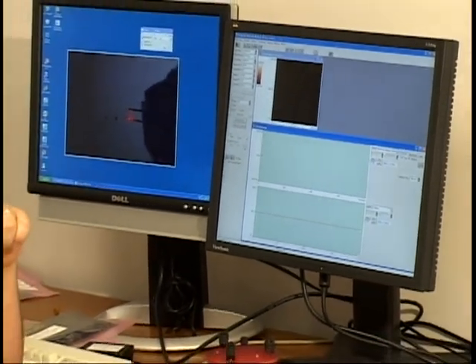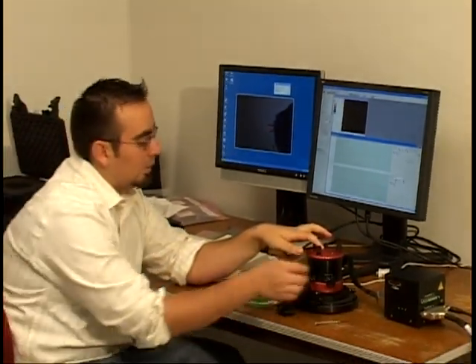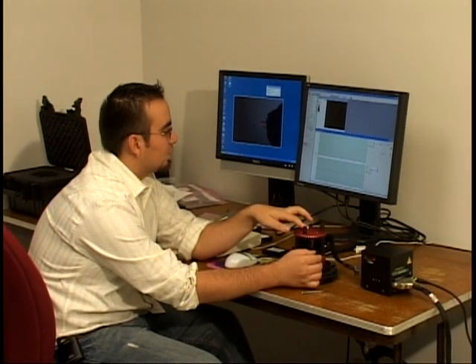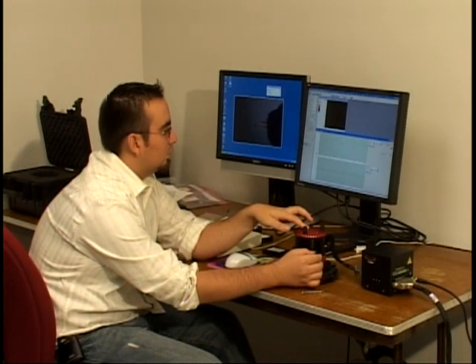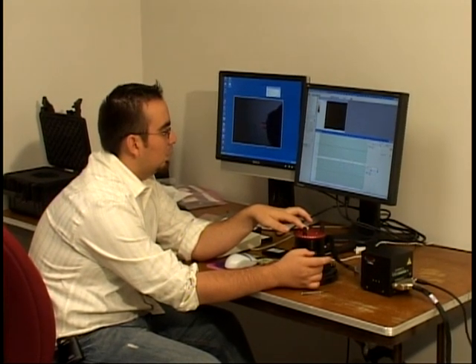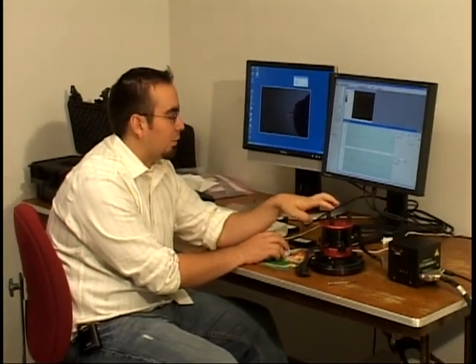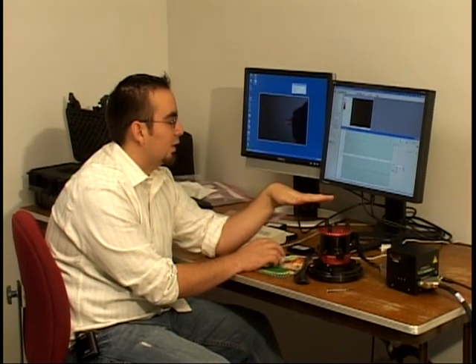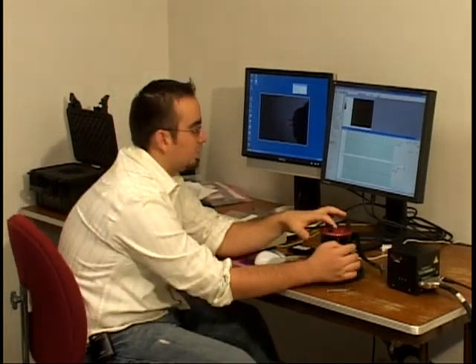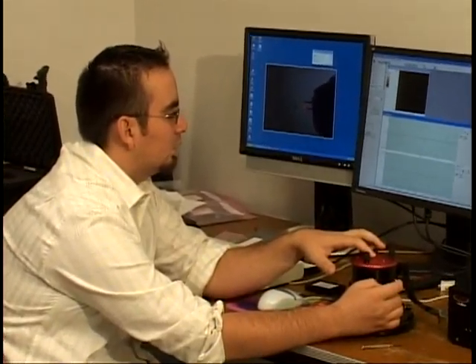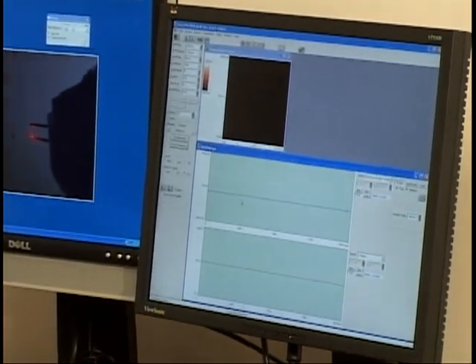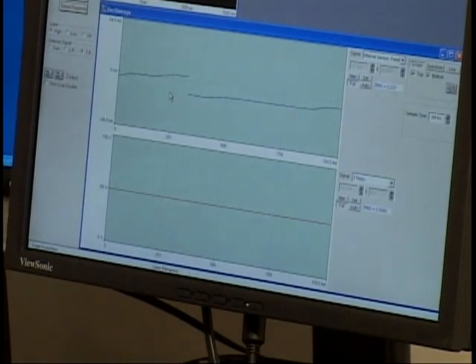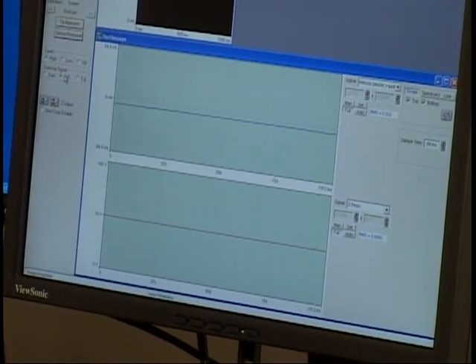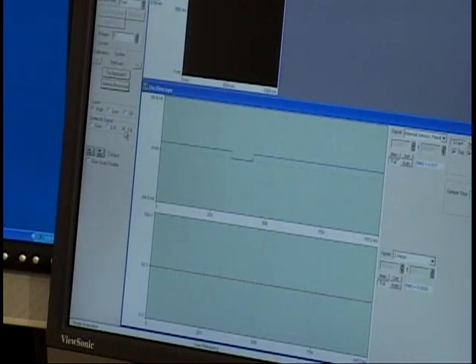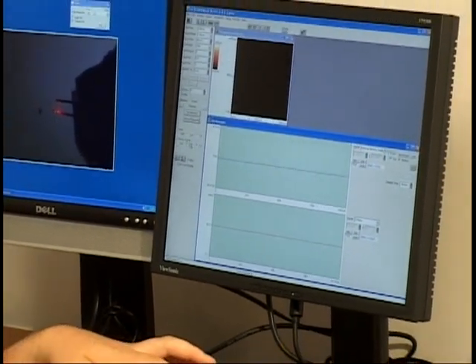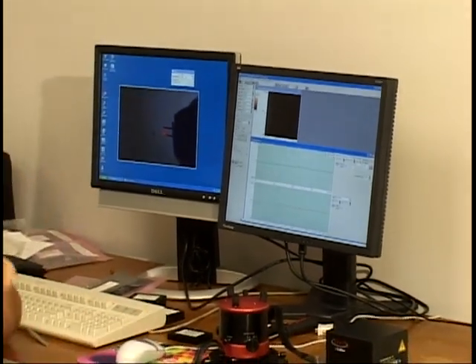Go to the top bottom knob now. Top bottom signal on the detector signal box. And do the same. So this one's like super sensitive. And pull it out again. Because the angle of the mirror might be a little bit off, you might have changed your left-right alignment, which you did. So go back to left and right and readjust. So readjust them both until you get to a point where they're both aligned. That's good. That's good.